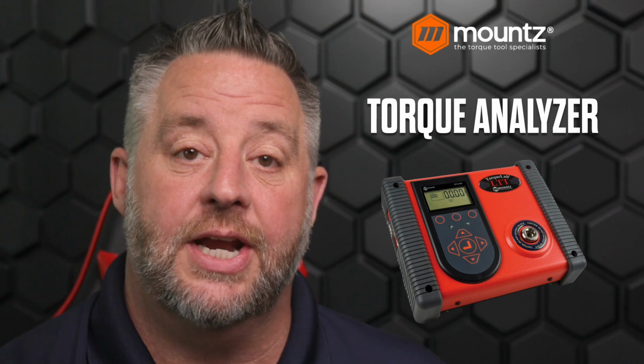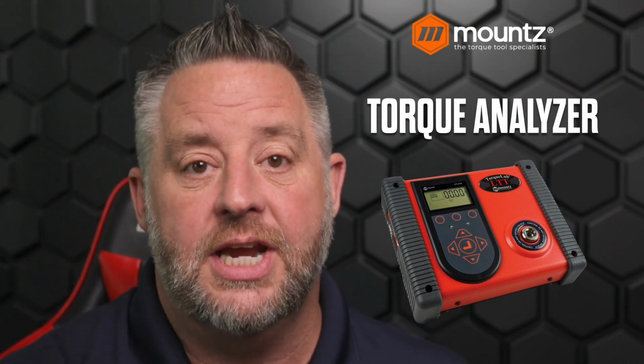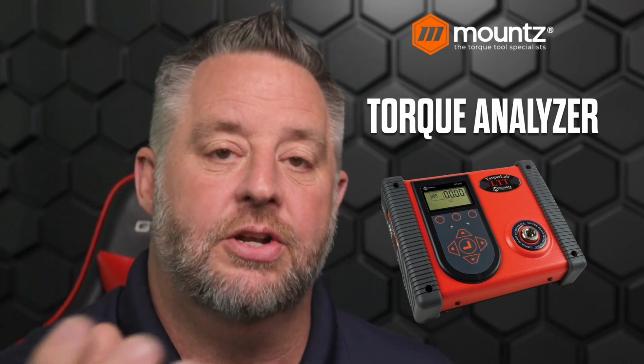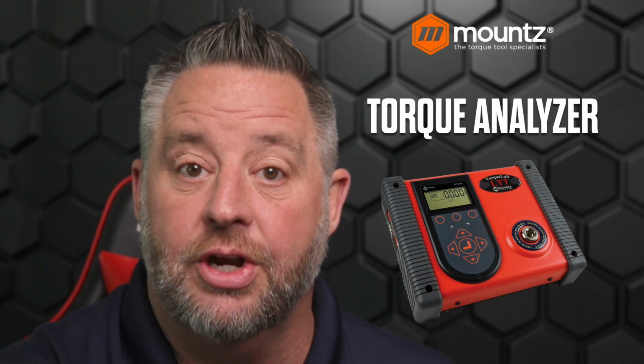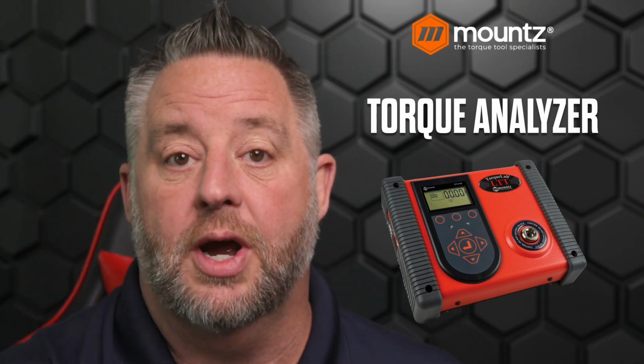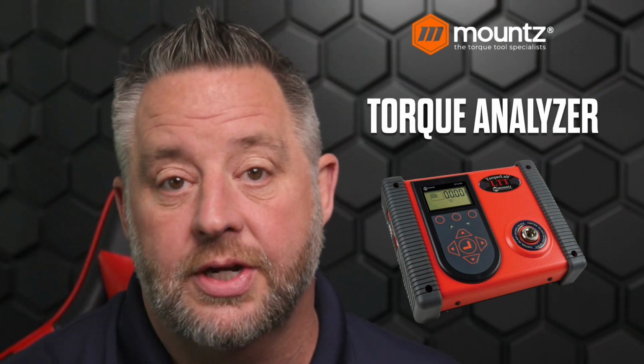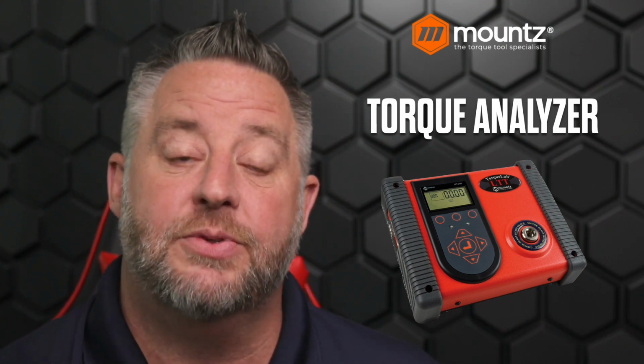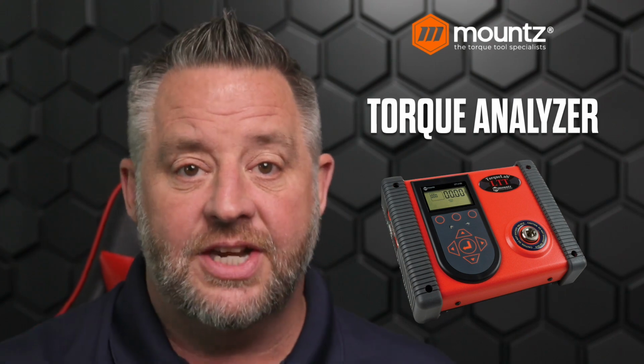Now, we can also measure torque with the use of a torque analyzer. And the torque analyzer basically takes an analog signal and converts it to a digital signal that we can use to measure tools on torque assembly products through different types of sensors. And these sensors use what's called a strain gauge.